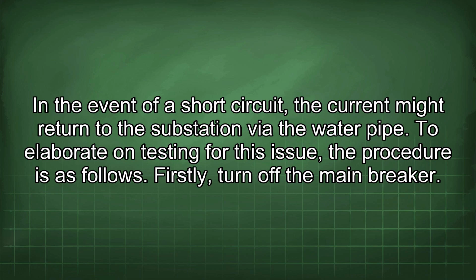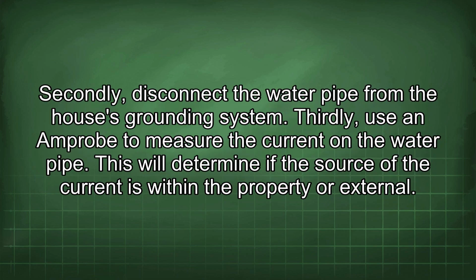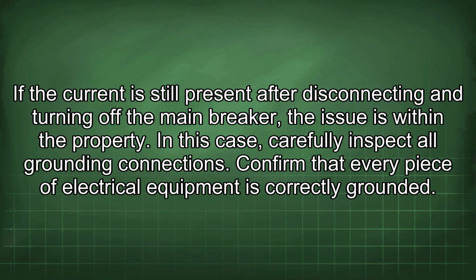Firstly, turn off the main breaker. Secondly, disconnect the water pipe from the house's grounding system. Thirdly, use an Amprobe to measure the current on the water pipe. This will determine if the source of the current is within the property or external. If the current is still present after disconnecting and turning off the main breaker, the issue is within the property.